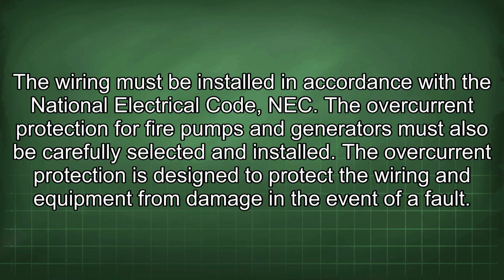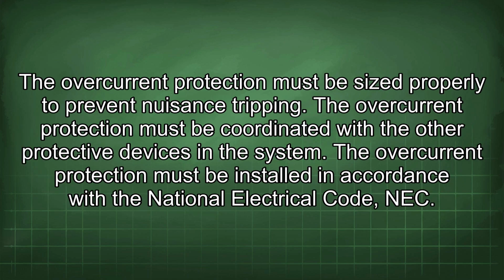The overcurrent protection for fire pumps and generators must also be carefully selected and installed. The overcurrent protection is designed to protect the wiring and equipment from damage in the event of a fault. The overcurrent protection must be sized properly to prevent nuisance tripping. The overcurrent protection must be coordinated with the other protective devices in the system. The overcurrent protection must be installed in accordance with the National Electrical Code (NEC).